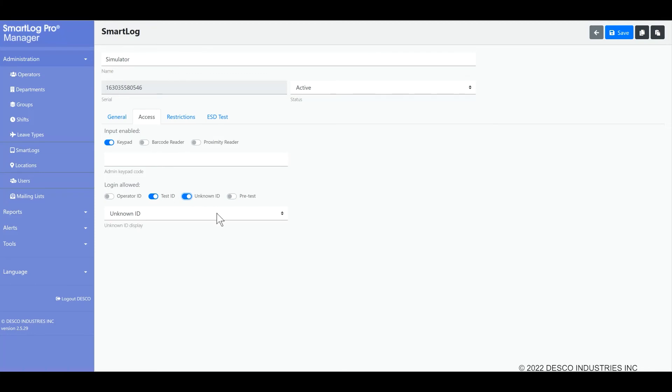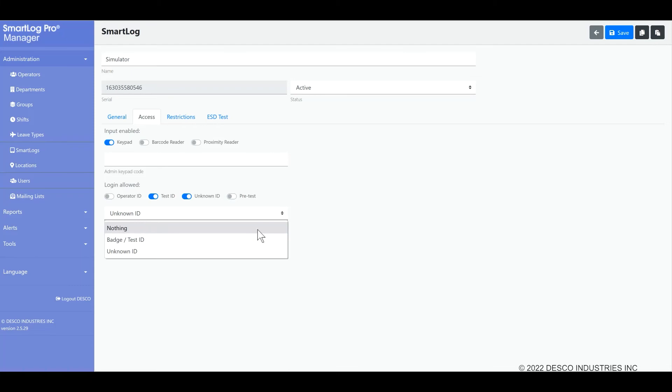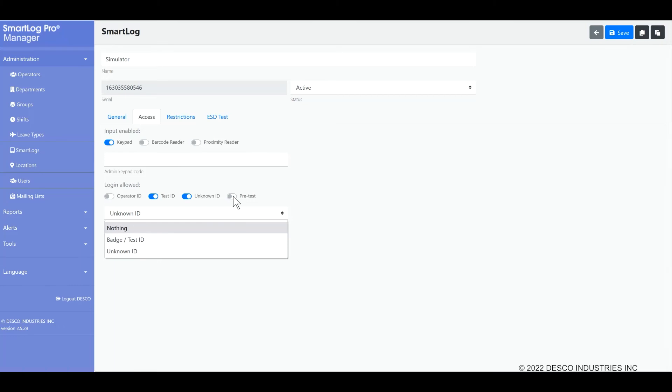If you allow unknown IDs, you may select what is displayed on the screen. Badge test ID, for example, is useful when using badges because it will show you what the reader has determined the card number to be. There is also a pre-test option here that may be enabled. This allows operators to perform a test by simply touching the test button on the SmartLog Pro SE without identifying themselves first. This may give an unidentified operator access, so please be careful when using this setting.